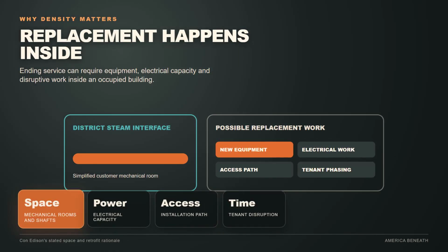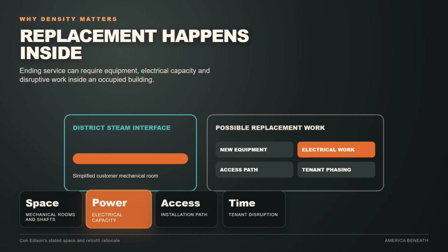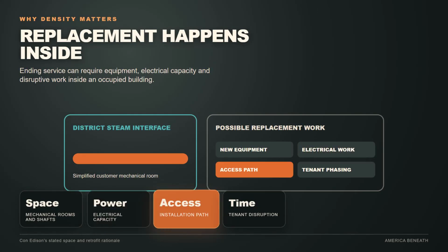Consider a simplified replacement. The owner may need new heating equipment, pumps, electrical work, controls, and a different path for hot water. Cooling equipment may need to change too. Heavy components must enter the building somehow. Existing tenants may need service interruptions. None of that makes replacement impossible. It makes it a building project rather than a utility cancellation.